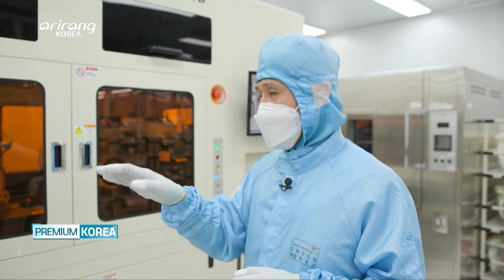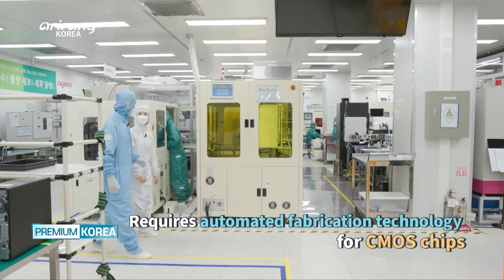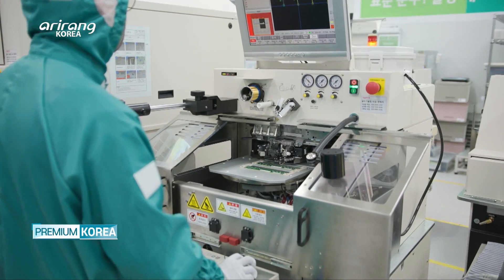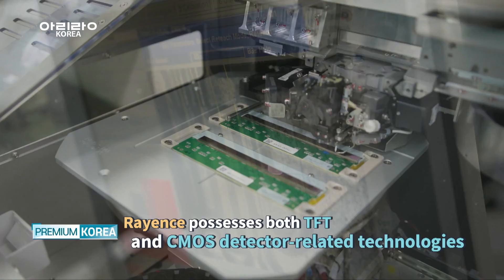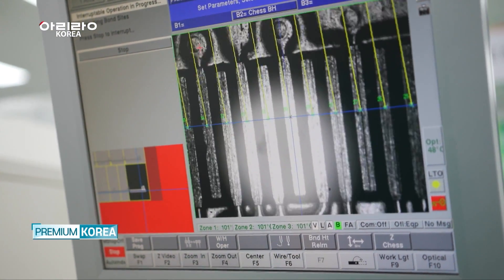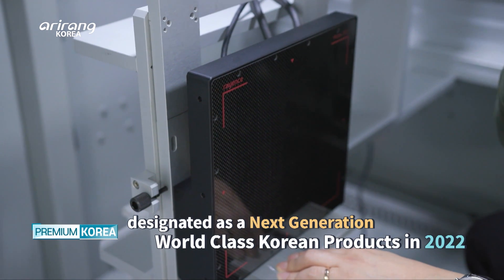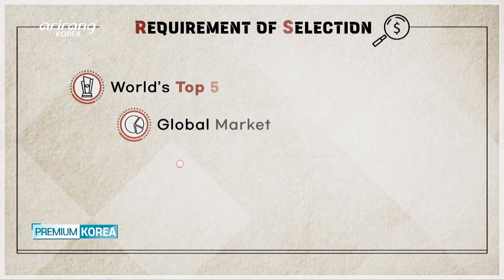Unlike regular camera modules and semiconductors, the CMOS chip and the X-ray detector requires chip fabrication technology, with everything coming down to the level of automation. Rayence is the only Korean detector manufacturing company to possess technology for both thin film transistor detectors and CMOS detectors, which is a rare achievement among global players. Based on this technology, it has succeeded in mass-producing MIDAS2121, subsequently designated as a next-generation world-class Korean product in 2022.